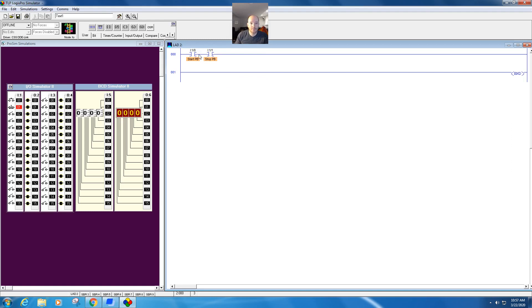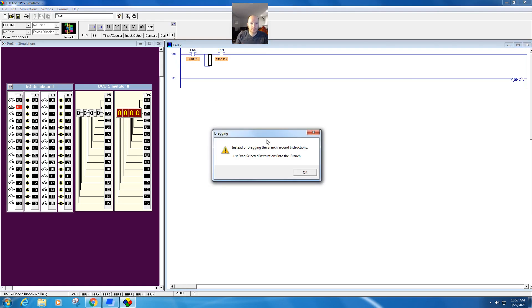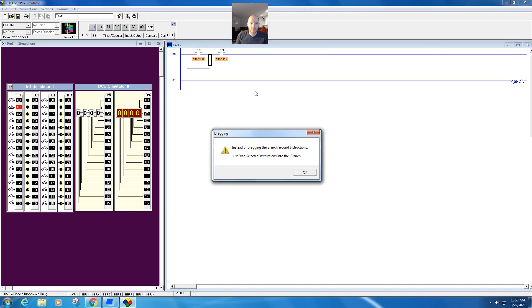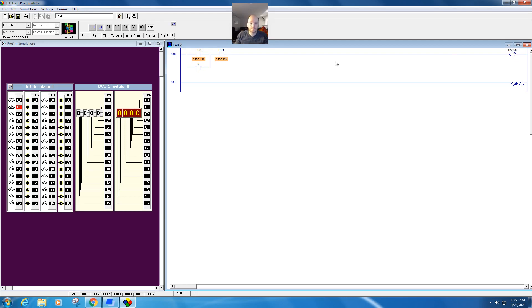Let's go ahead and put some memory in here around my start button. Drop this around. So we want to bring this into here. It doesn't seem to, doesn't like the idea of you dragging this around. That's actually a super important feature. We'll drop a memory in here. We'll come here and I'm just going to add a B3 to this real quick. So B3 colon zero, forward slash zero, enter. I'm going to drag that memory right down to there, which is another awesome feature. That can save you some serious time.